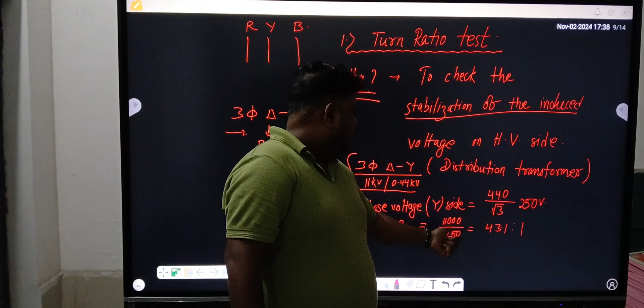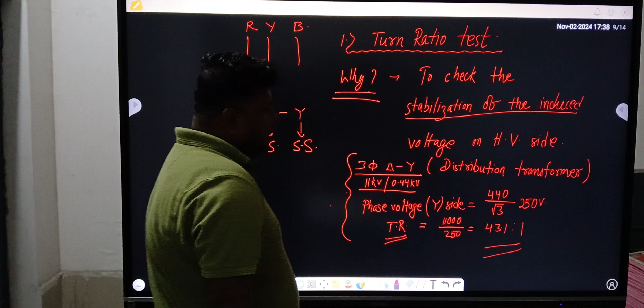So turn ratio on HV, already it is rated as 11 kV, that is 11,000 volt, and the volt we have got by converting the phase voltage into star is 250. So 11,000 by 250, we got this ratio 43.1 is to 1. This is the calculated value, 43.1 is to 1. Now, how can we conclude that this turn ratio is correct or not? This 43.1 is to 1 should be same for other tappings as well.